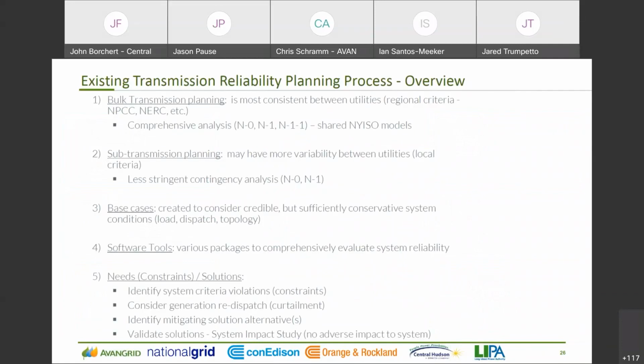A reliability analysis on the bulk power system has limited variance between utilities, as there's regional criteria we have to adhere to. These studies are subject to a comprehensive N-1 and N-1-1 analysis. N-1 means a single contingency or fault occurring, while N-1-1 is a contingency followed by a second contingency occurring. Utilities have to share their contingency events with other transmission owners so that all potential events are covered, coordinated with the NYISO. For example, even though we're only studying our own area, we would run contingencies located in other utilities' service territories as well.